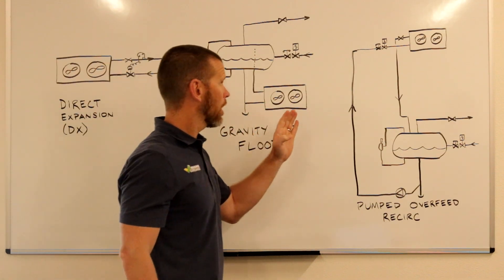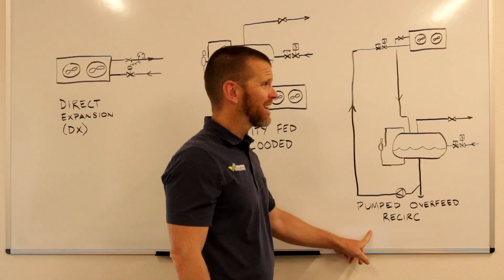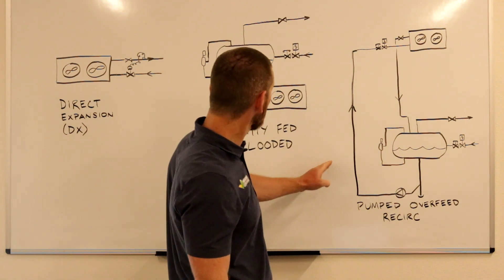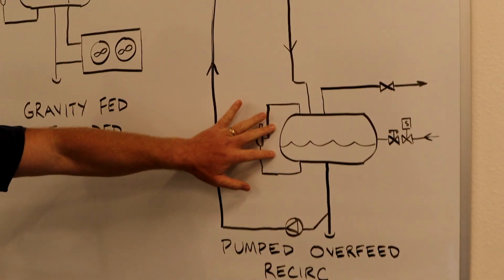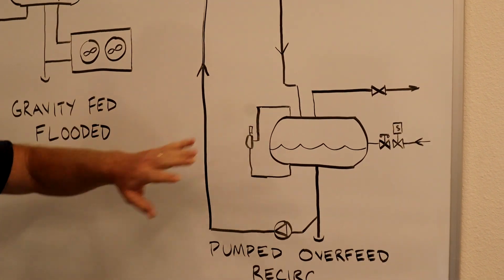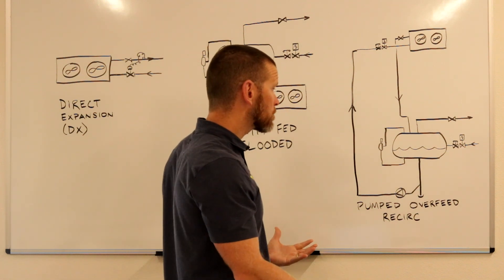A third option is our pumped overfeed or recirc system. This is very similar to the gravity flooded system in that we have a vessel again employed. We don't call this vessel a surge drum, typically it's called a recirculator, sometimes a low pressure receiver.